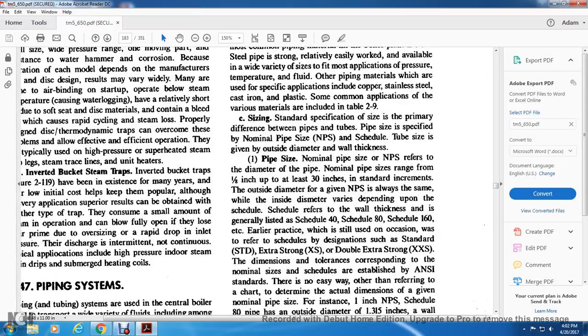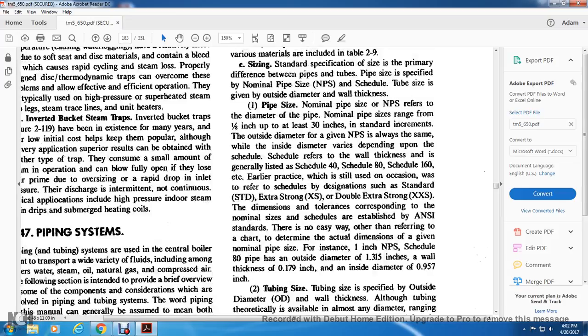Size. There are standard specification sizes, and this is the primary difference between piping and tubing. Pipe size is specified by the nominal pipe size, or NPS, and schedule, while tube size is given by outside diameter and wall thickness. Pipe sizing. Nominal pipe size. The nominal pipe size refers to the diameter of the pipe. The nominal pipe size ranges from 1/8 of an inch up to 30 inches in standard increments. The outside diameter for a given nominal pipe size is always the same. The inside diameter varies depending upon the schedule.